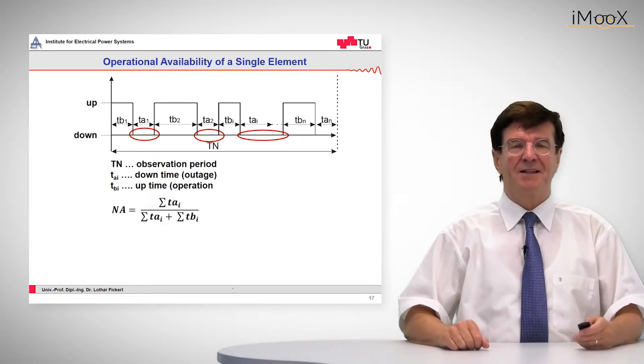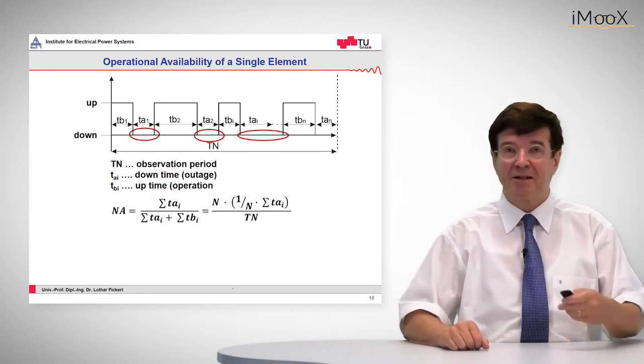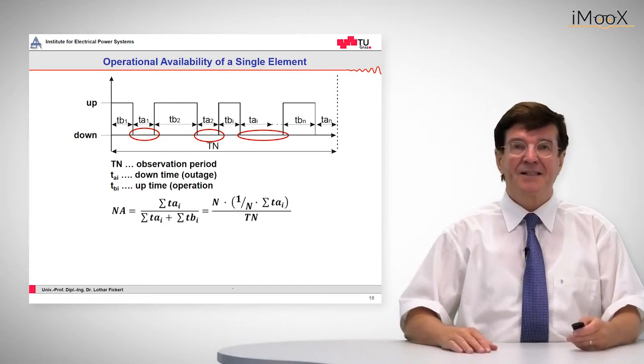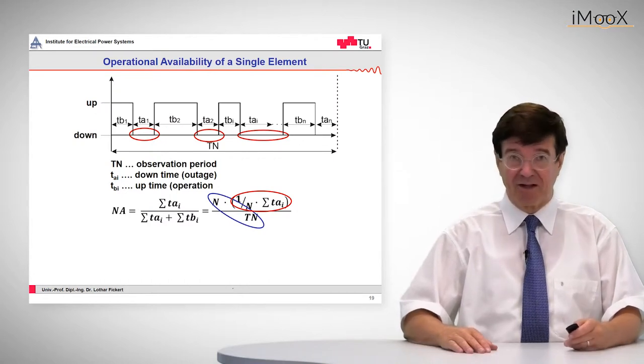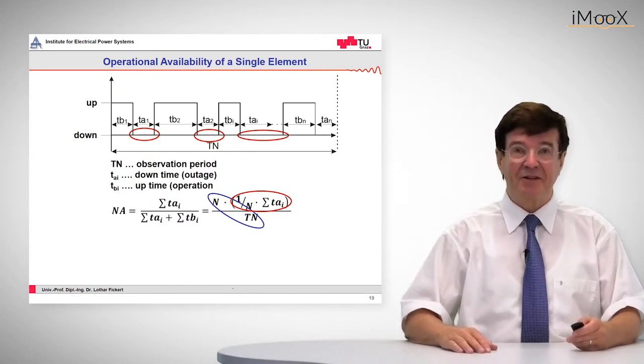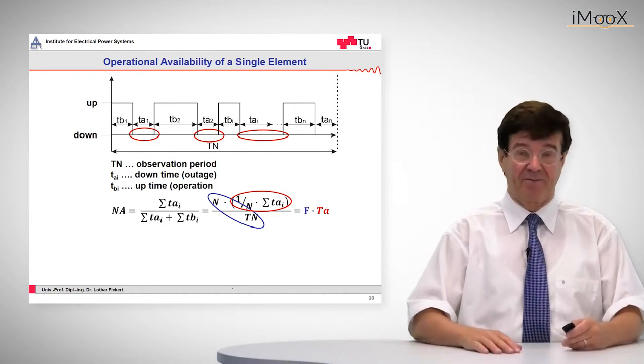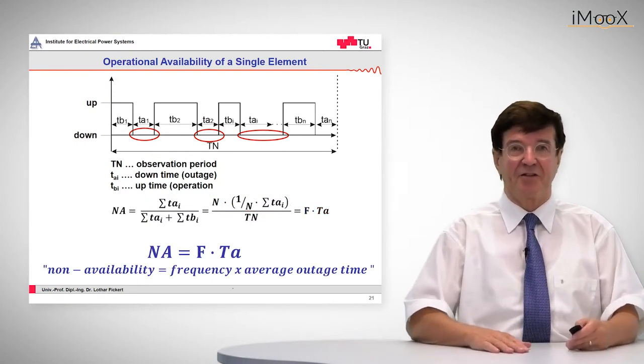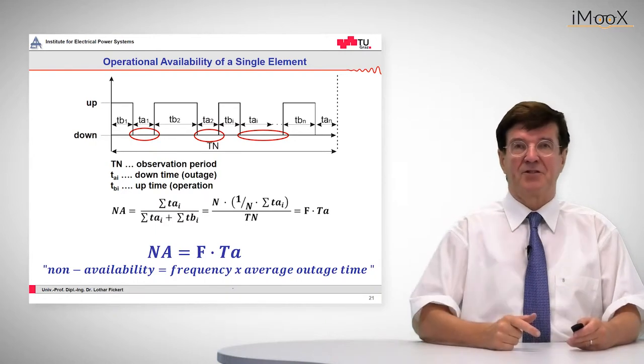By dividing and multiplying by n, we can rearrange that n divided by the total observation time is the frequency multiplied with the average outage time. So we come to the law of non-availability: non-availability is the product of frequency and the average outage time.